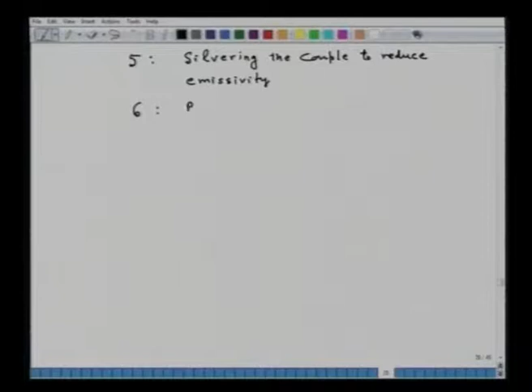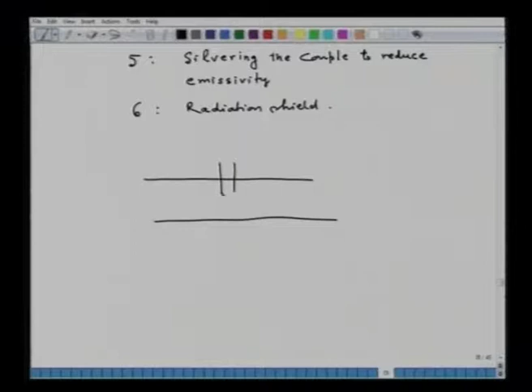Say, for example, in one of the cases, what we can do, this is the furnace. Say we insert a thermocouple. This is the bead of the thermocouple, and these are the wires. And what we do here, this is the gas flow direction, and this one is connected to an aspirator or vacuum. This is a shielded high velocity thermocouple suitable for gas temperature measurement. Here this is the furnace, or this is the duct, or whatever you want to say. So the gas is flowing, it is sucked. So this is the way of minimizing the error.